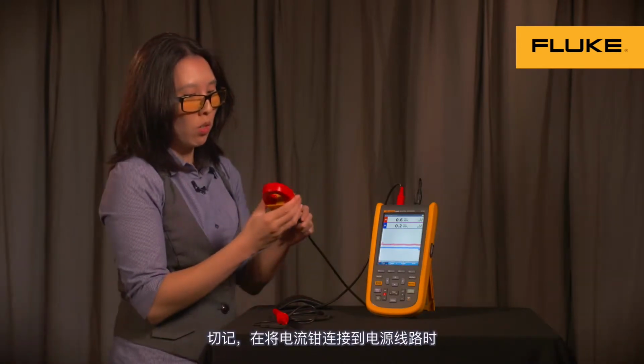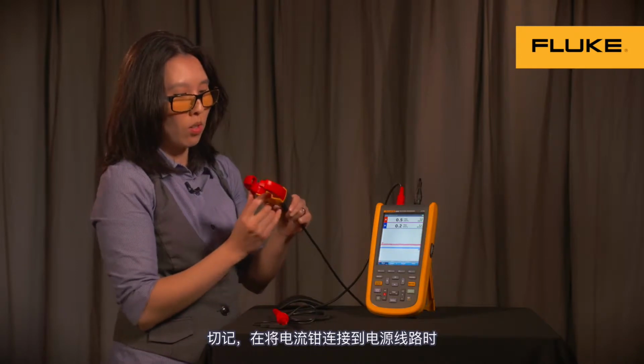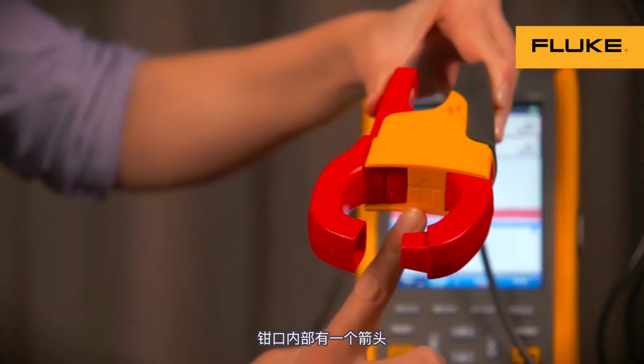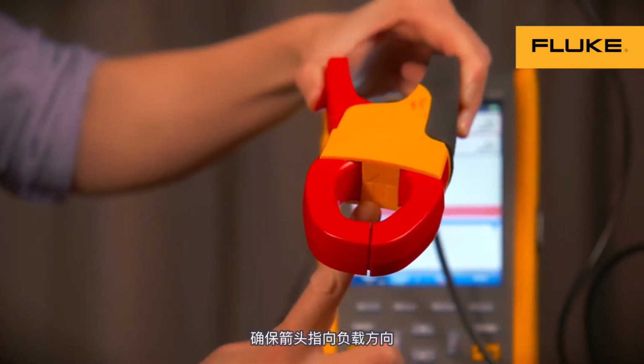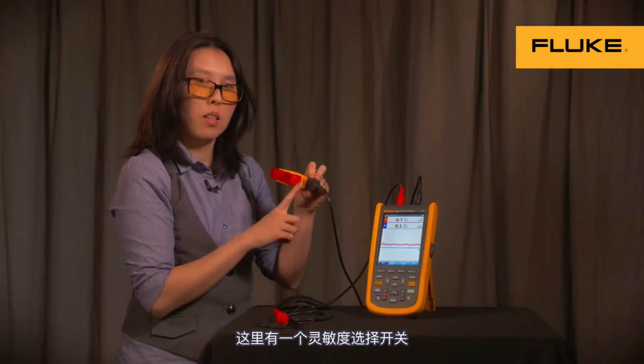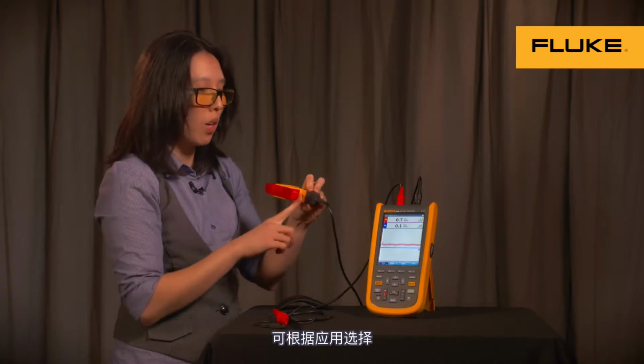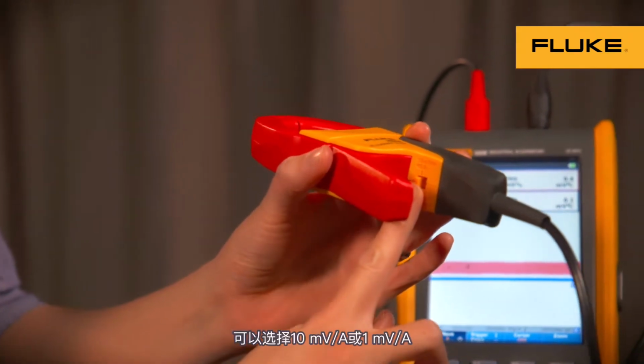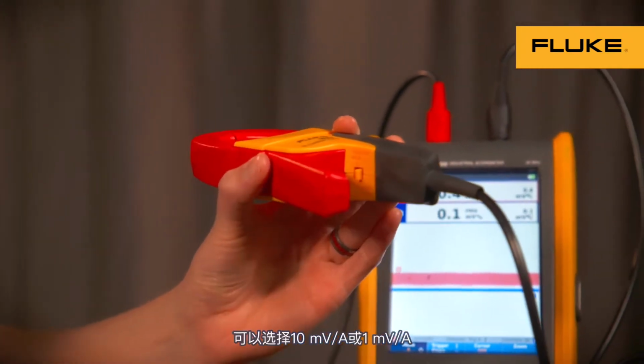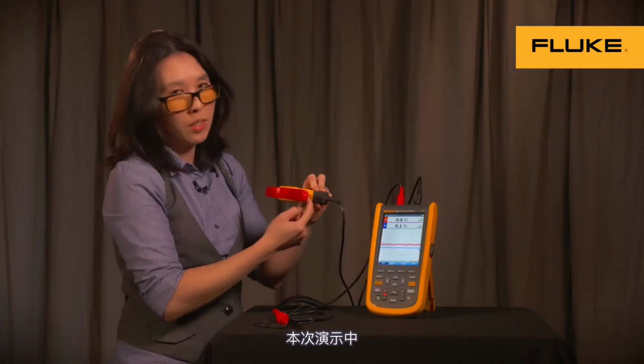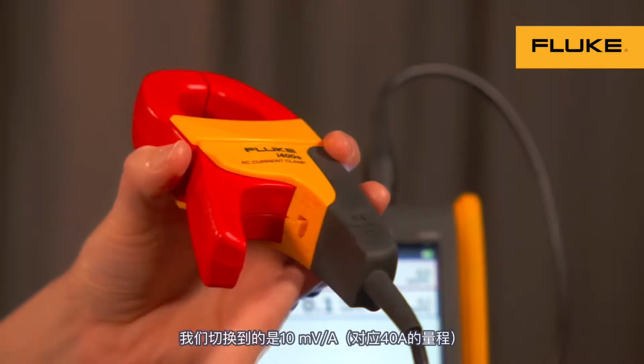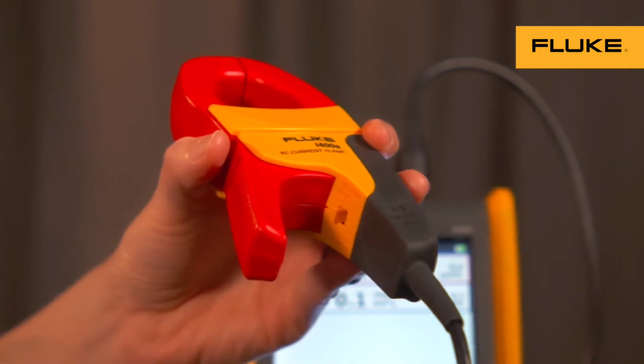And keep in mind, when you're clamping on to the current source, to this arrow right here on the inside, make sure that it's pointing towards the load. And also make sure you have the right sensitivity selected for your application. You can choose between 10 millivolts per amp or 1 millivolt per amp. In this demonstration, we'll have it switched to 10 millivolts per amp.